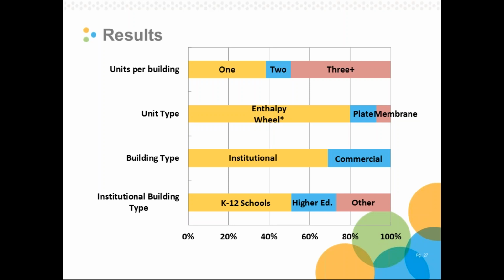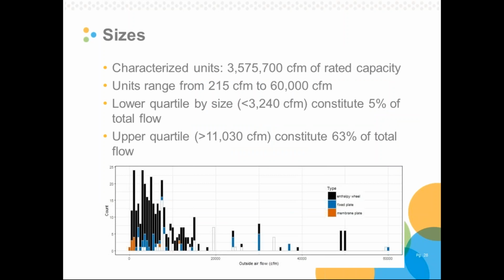In terms of the building types, we found that energy recovery is most often to date implemented in institutional buildings, about 70%. About 30% of the implementations are in commercial buildings. From the information we have, we know that it's implemented in commercial buildings that have unusually large outside air requirements. This would be auto shops, casinos, gyms, sports facilities, that kind of thing. In terms of the institutional buildings, about half of them were implemented in K-12 schools, about a quarter in higher education buildings, and the remaining quarter was spread among a lot of different municipal and state facilities.